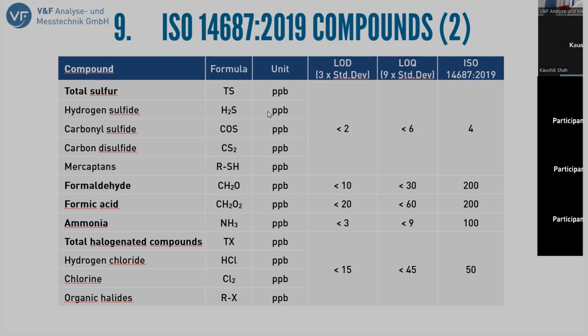Now, what is special about this device? If you look into these regulations, there are standard methods available for most of the compounds that are stated, but typically this would require a rack of about 5 to 6 analyzers in order to be able to do that quantification. So what we wanted to provide here is a singular housing for instruments which can do the analysis all at once and in real time if necessary. With the HydrogenSense, we have managed to do that. The analyzer is a real time concept, but since we are looking at very low detection levels, we're talking about an analysis time of roughly 15 minutes in order to quantify everything that is required within the ISO regulation.